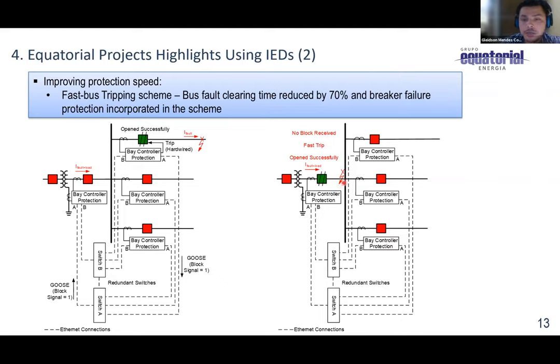In a different situation, if I have a fault in the bus bar, the main relay identifies that no feeder sends a signal, so it knows that the trip is in this area. So instead of using 300, 500 milliseconds to trip, it does this job in 50 milliseconds. Reduce the accumulative damage to the transformer.